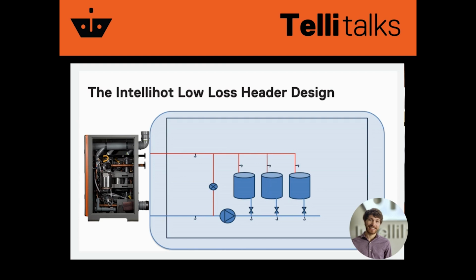In our system, what that means is primarily what's going to happen, and as water comes in for the cold water line at the bottom of the unit, by the way, this is an IQ 751 we've got on the screen here. Water is coming in through your cold water supply at the bottom and being forced by the pump through the heat exchangers. As flow goes through the heat exchangers, it does drop a little bit of pressure, and then it comes out and gets delivered to the fixtures.